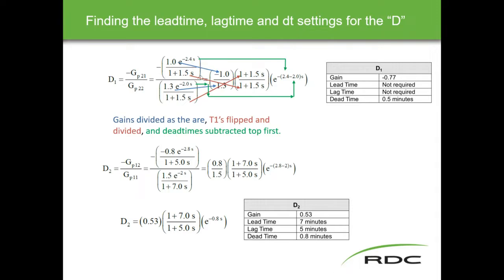The process for finding lead time, lag time, and dead time settings: I've color-coded the arrows this time. Gains are divided — the upper gain divided by the lower gain. The T1 times get flipped — top goes to bottom, bottom goes to top; in this example they're the same value, but in any other case they'd obviously be flipped. Dead times are subtracted top first: 2.4 minus 2.0. There's no lead time or lag time required in this example because the values are small enough to cancel out.